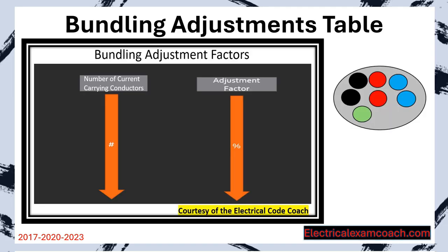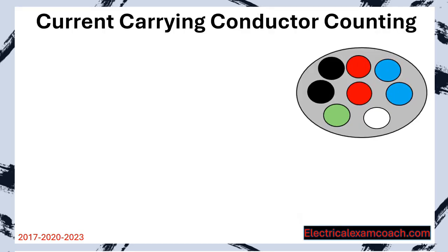Up until this point we've had all hot conductors inside of our conduit. But what happens if we add in a neutral? Is it considered a current carrying conductor? What about grounding conductors — are they considered current carrying conductors? Let's learn how to count conductors now. We're only going to be counting the current carrying conductors. You may get a question on your exam that gives you the number of conductors — that's easy, you're going to go to the tables and do the math. But you may get a question that asks you in a scenario of wires how many of them are current carrying conductors.